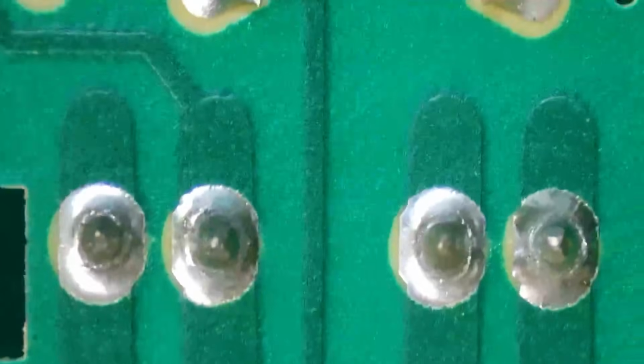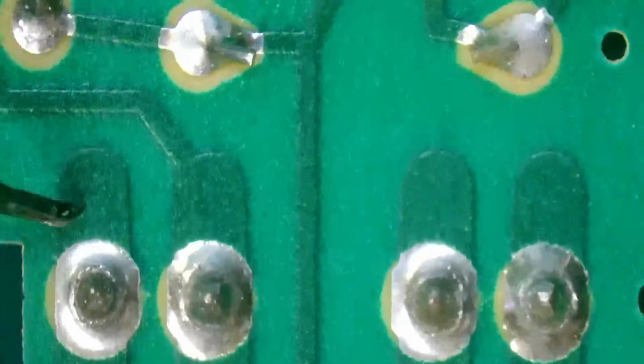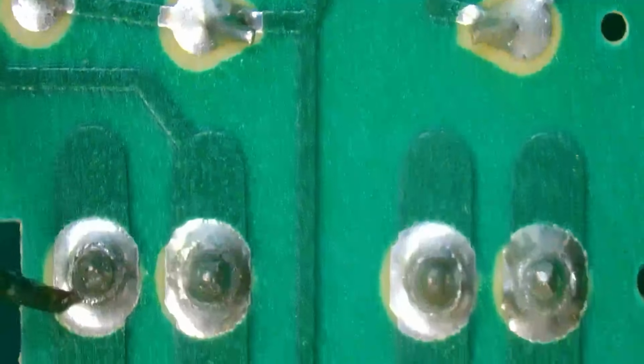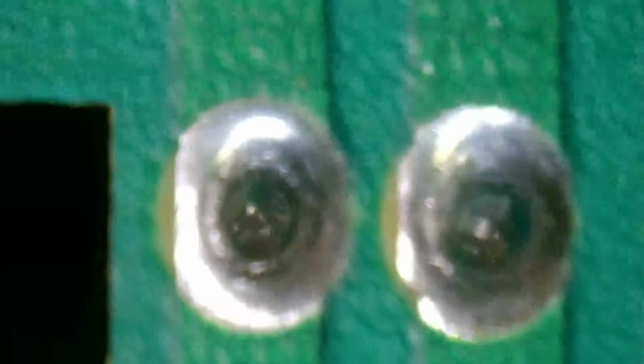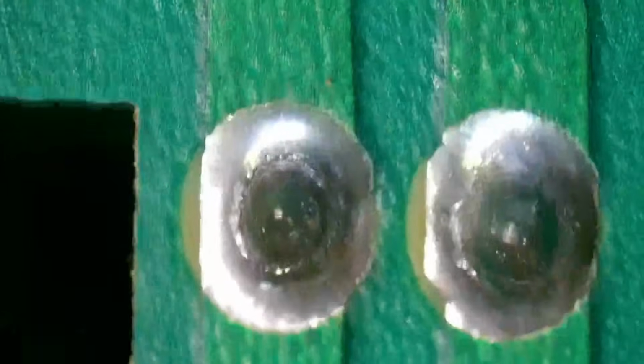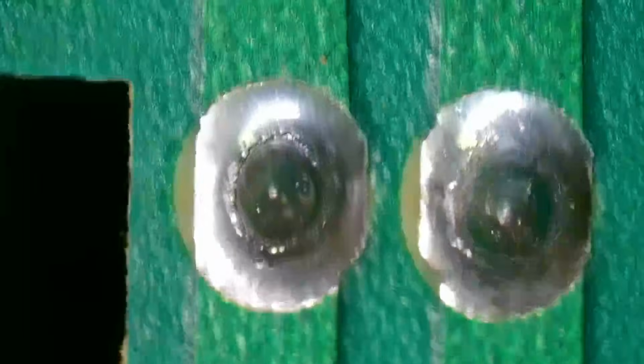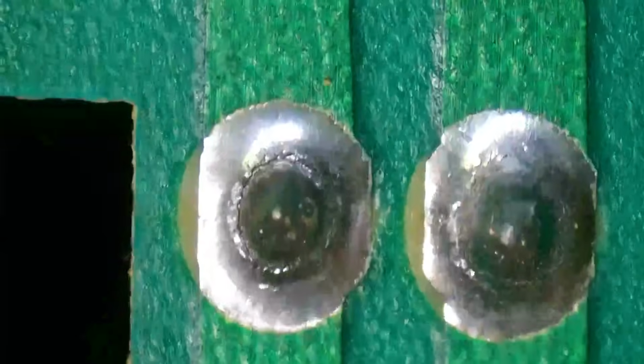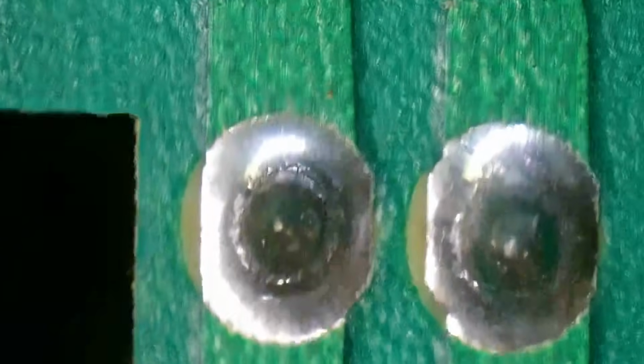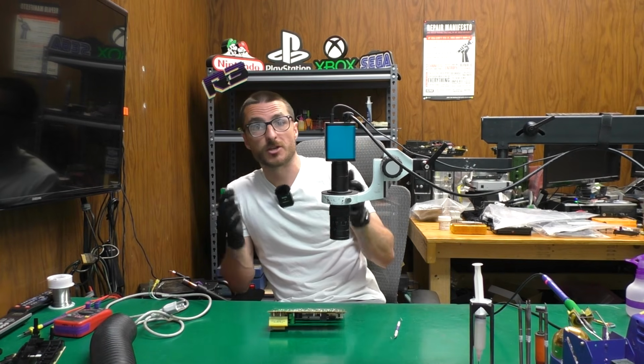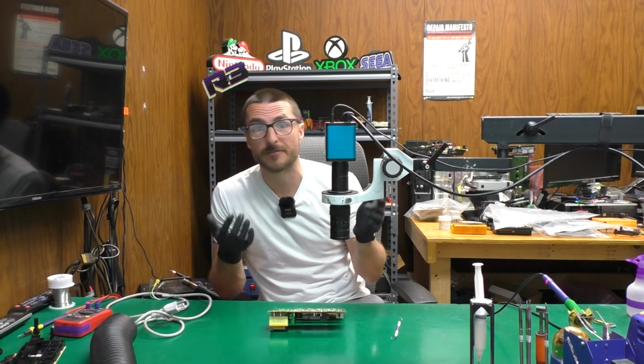And right here is the back of the connector that our sensor plugs into. As you can see, there is a bit of a ring forming around all of these joints. And if we zoom in a little bit more, we'll really see that there is actually separation between the joint and the pin. I'm physically pushing on the pin on the backside right now, and you can see that pin is able to move within that joint, which means there is full separation of the pin from the connection. When that happens, of course, the controller board can no longer detect or communicate with the temperature sensor, which is why we get that F3 error code.